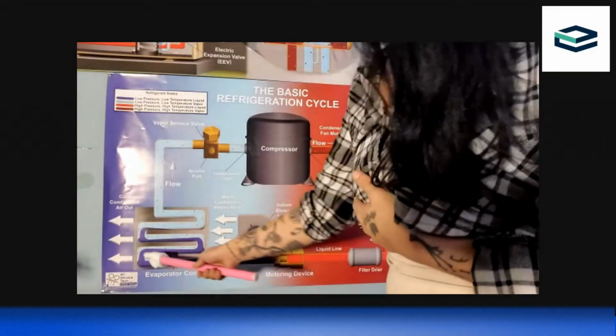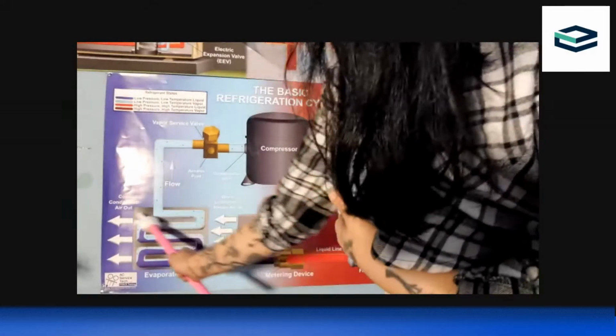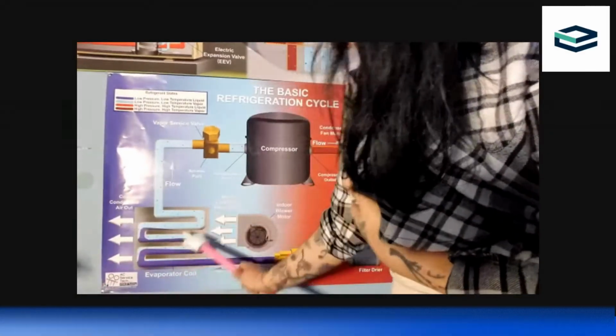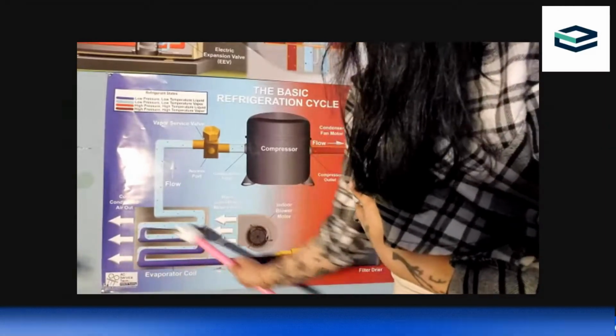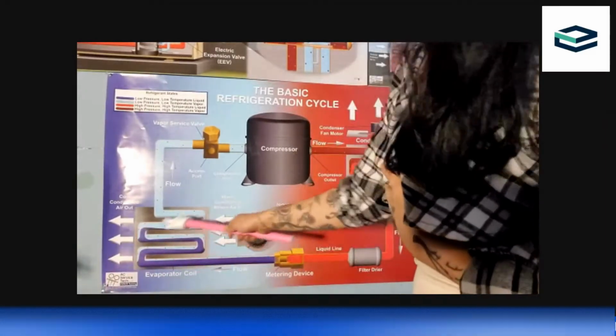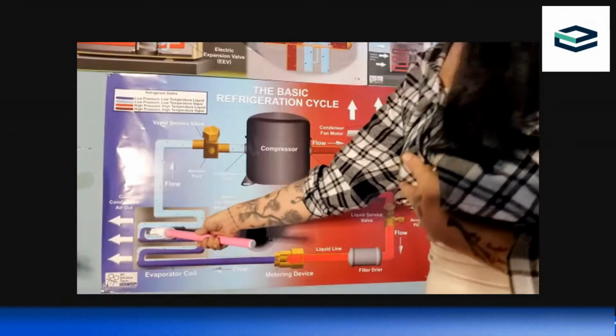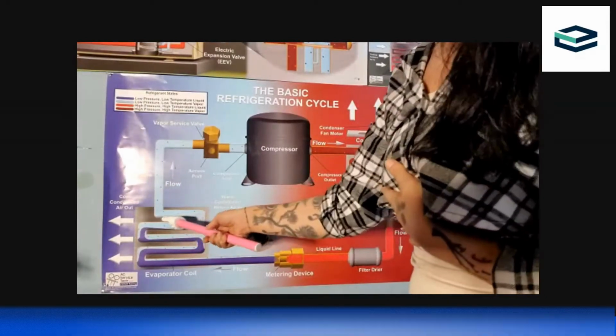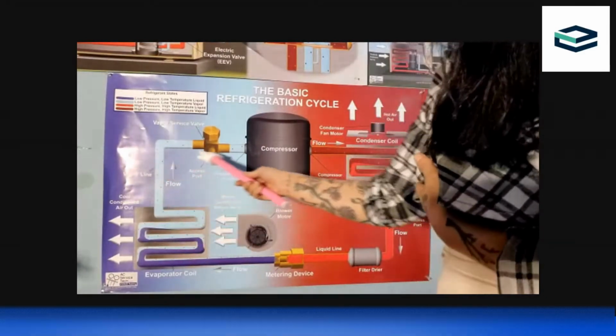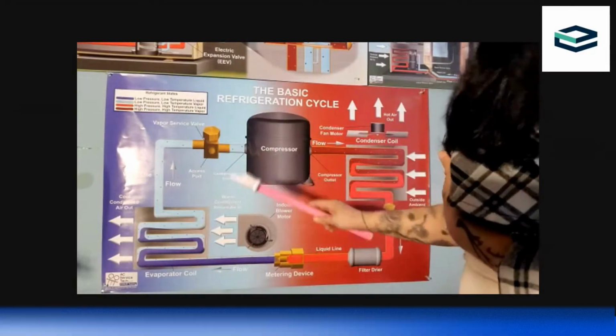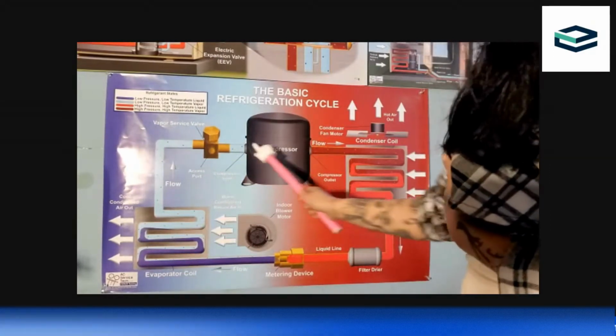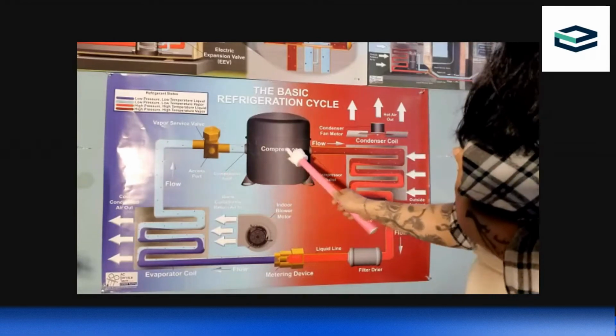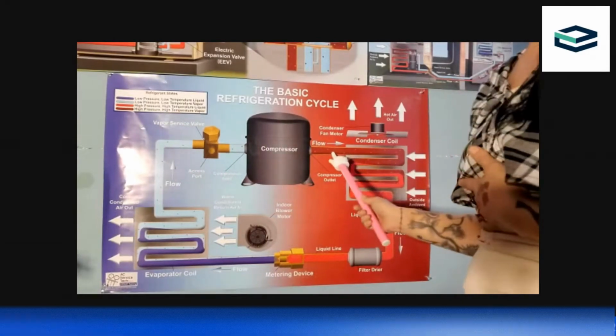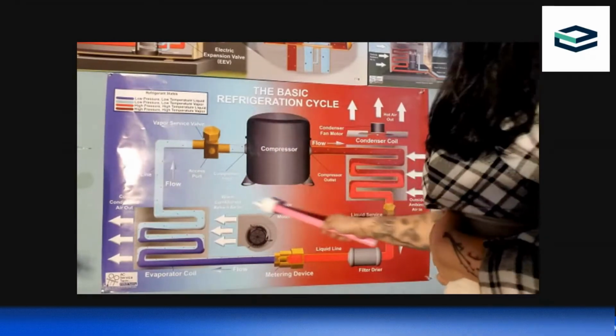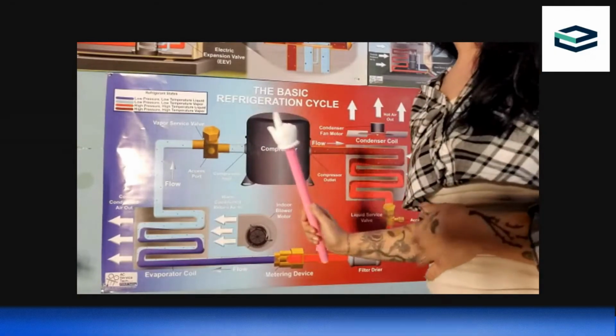So as it evaporates, it blows out that conditioned air. So we have a cooler temperature coming off of this coil into your home. And then it turns into a low pressure, low temperature vapor, and then comes back to the compressor. So as you notice, it's always a vapor when it comes to the compressor, and then it's always leaving as a vapor as well. This compressor cannot see liquid refrigerant, it will break.